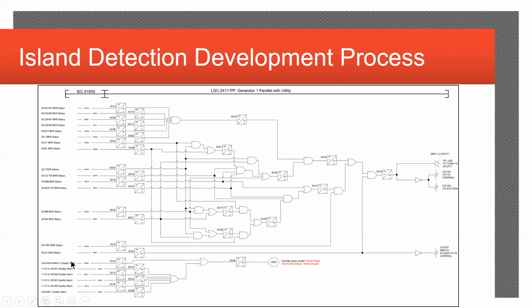You can see we have some quality bits down here, and obviously with not having all of the appropriate information from all of the circuit breakers, you could potentially have the system come up with an erroneous state. And so essentially the safe thing to do here is to really do nothing. So if you lose communications to an IED, the system wouldn't make an island determination under those conditions.